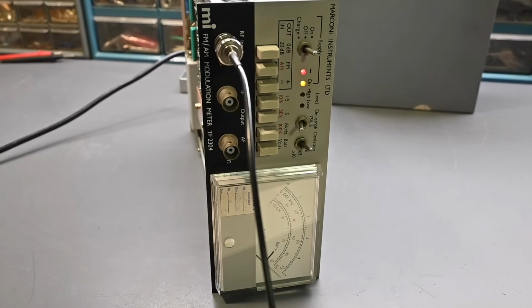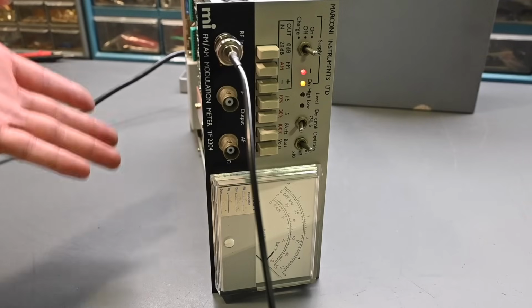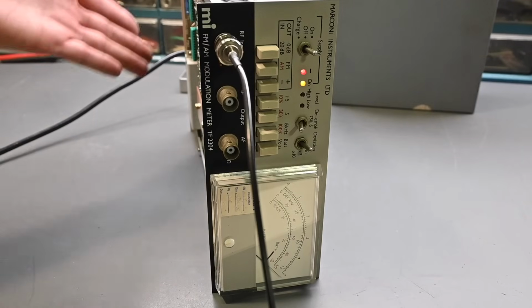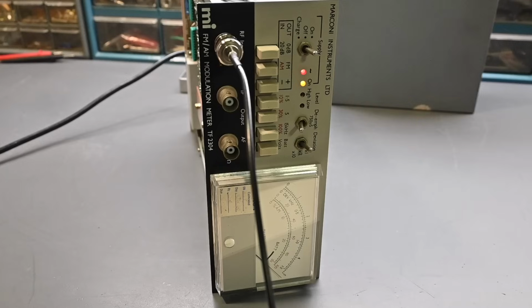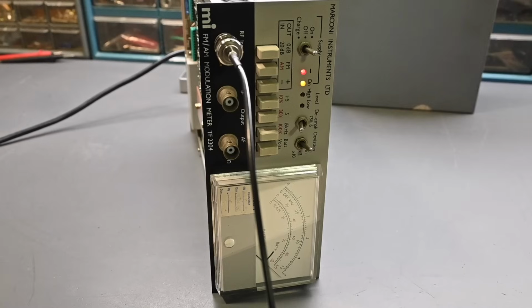Also, if you're following along, you're definitely doing so at your own risk. You know, this is AC line powered, and there are exposed AC line voltages in the instrument with the cover removed. You need to be careful and not touch in the wrong locations. This is being powered off my isolation transformer for this testing as well. So again, if you're following along, take care, be safe. You are doing so at your own risk.